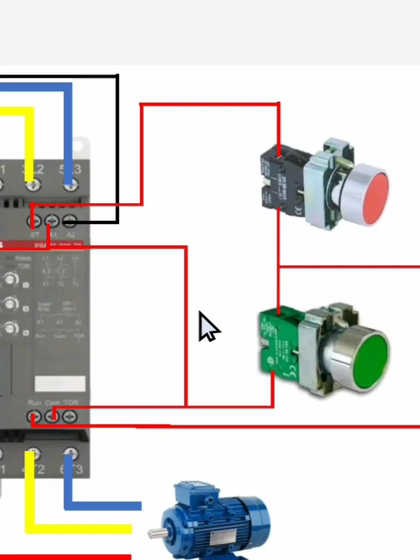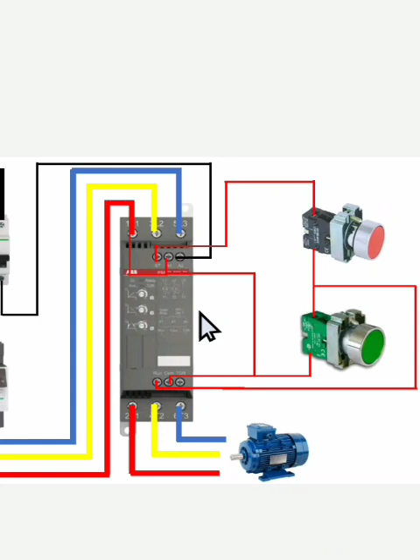I think that's it. It looks so simple, just make sure you follow the connection exactly as it is. This solves a lot of problems in the manufacturing industry. Sometimes when working with a star-delta setup or very large motors, the inrush current is very high and it trips the breaker, but with this soft starter, it starts smoothly.